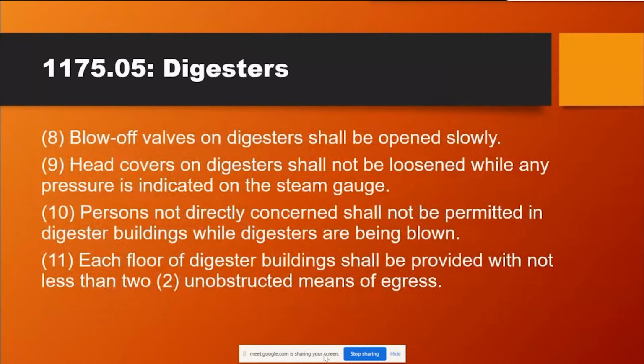Blow off valves on digesters shall be opened slowly. Head covers on digesters shall not be loosened while any pressure is indicated on the steam gauge. Persons not directly concerned shall not be permitted in digester buildings while digesters are being blown. Each floor of digester buildings shall be provided with not less than two unobstructed means of egress.